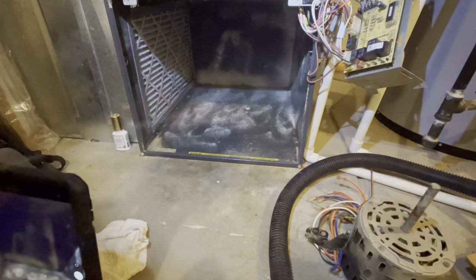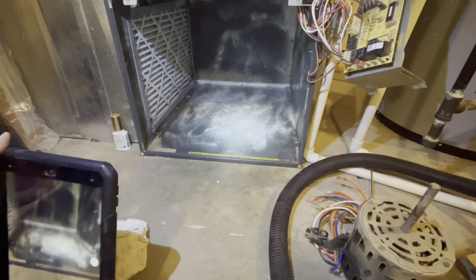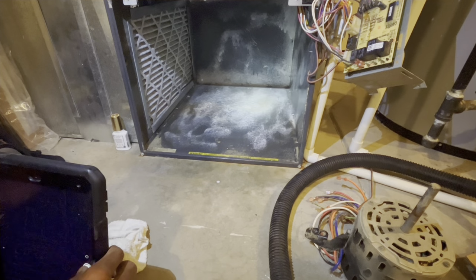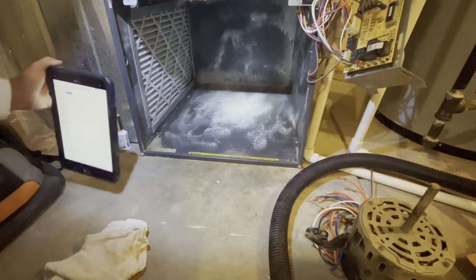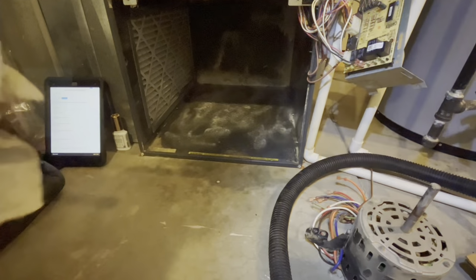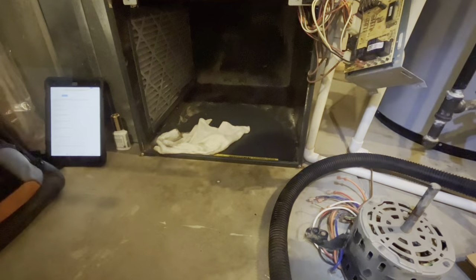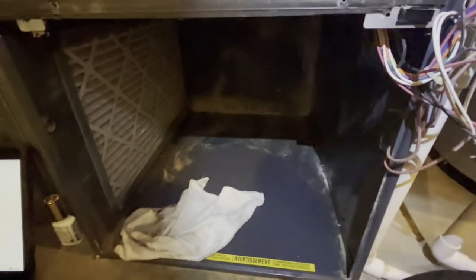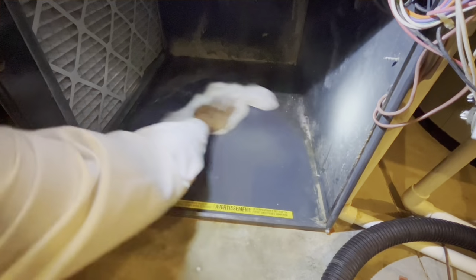Because the cleaner that you keep these systems, the better they run, the more efficient they run. It's better, cleaner air for you in your house. So all the way around, you need to get the system cleaned. We recommend it every year. Depending on the type of filtration system that you have, the better filtration system you have, the better it'll catch all the dirt and debris. So you may be able to extend that cleaning, but you definitely want to get it checked every year, especially with the age of it.